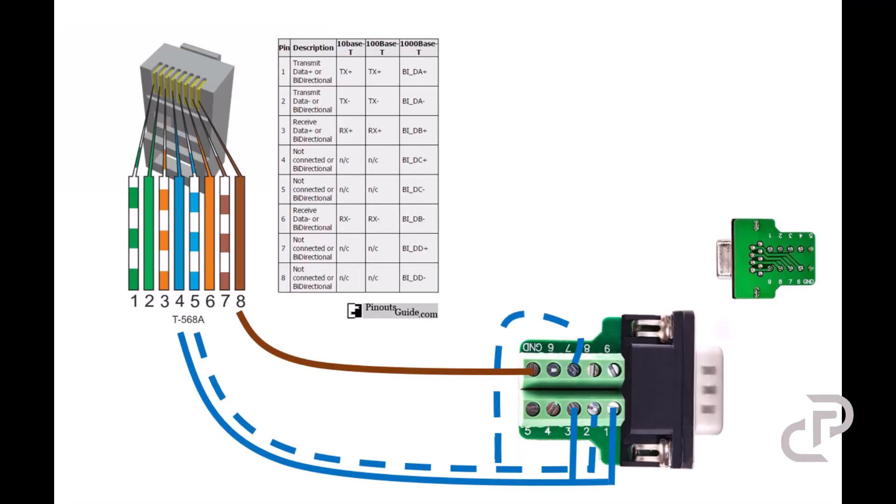Connection cable is connected to PLC by RJ45 connector, and from the other side is connected to DB9 female connector with this wiring. Take into account that pins number 2 and 7 is connected together in DB9 connector, and pins number 1 and 3 are connected together as well.